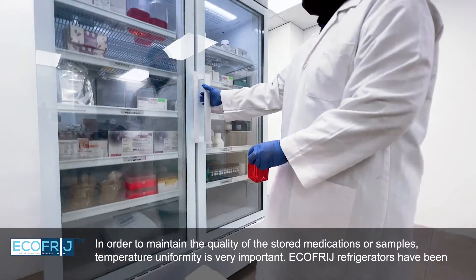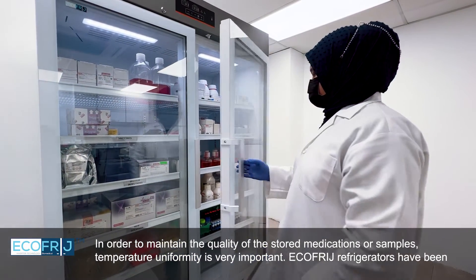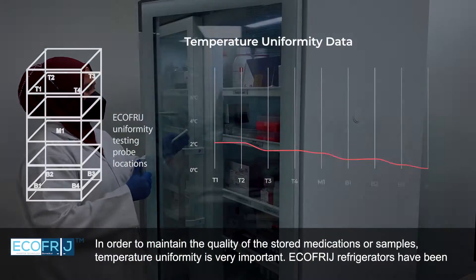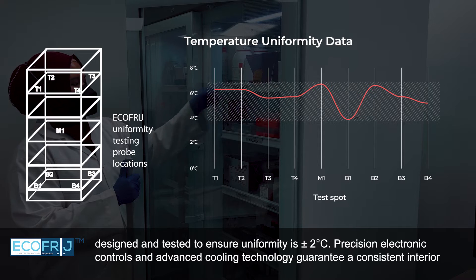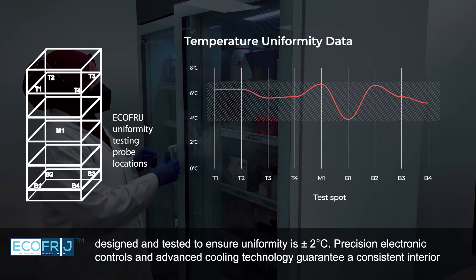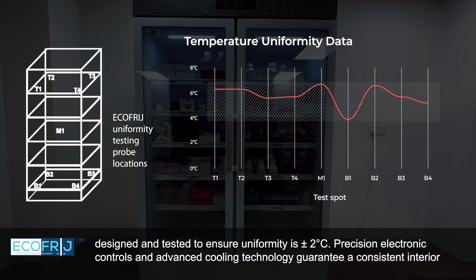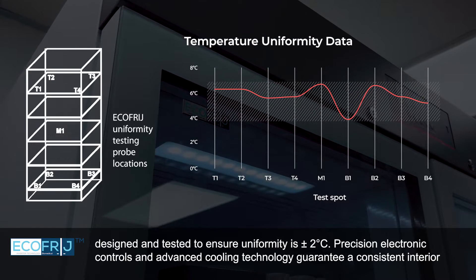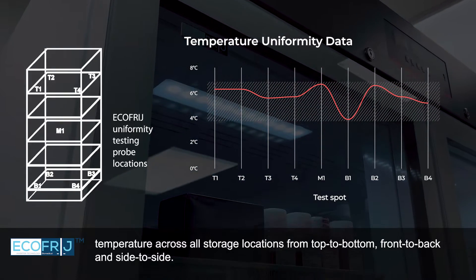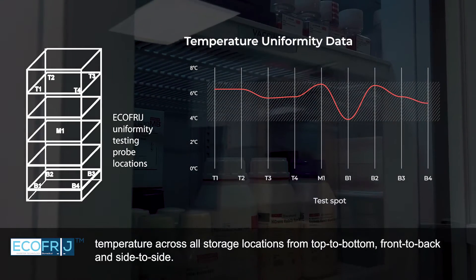In order to maintain the quality of stored medications or samples, temperature uniformity is very important. ECOFRIJ Refrigerators have been designed and tested to ensure uniformity of plus or minus 2 degrees Celsius. Precision electronic controls and advanced cooling technology guarantee a consistent interior temperature across all storage locations, from top to bottom, front to back, and side to side.